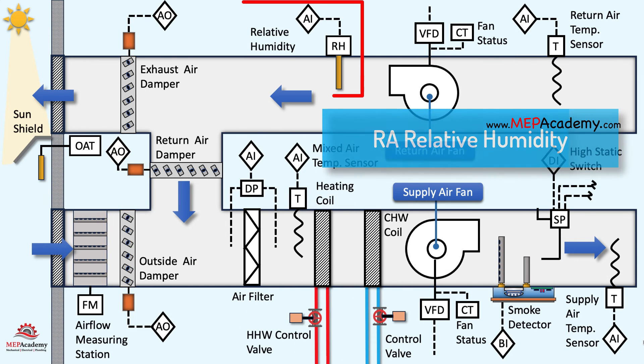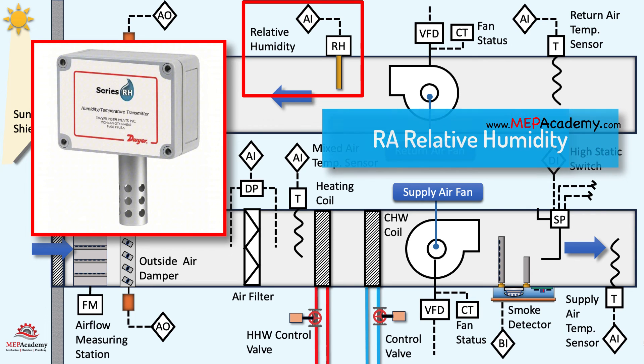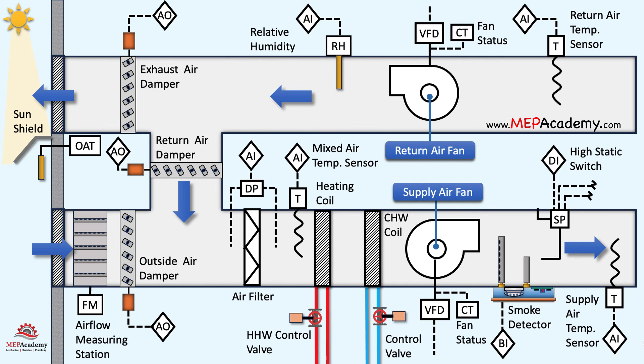The return air relative humidity sensor continuously monitors the relative humidity level of the air being drawn back into the HVAC system from the occupied spaces. The feedback from the sensor is essential for the control system to adjust the operation of humidification or dehumidification elements, such as steam humidifiers or cooling coils, to achieve the set point relative humidity. This control is crucial for maintaining a comfortable and healthy indoor environment.